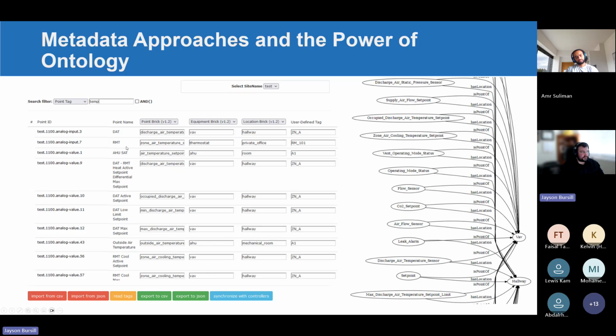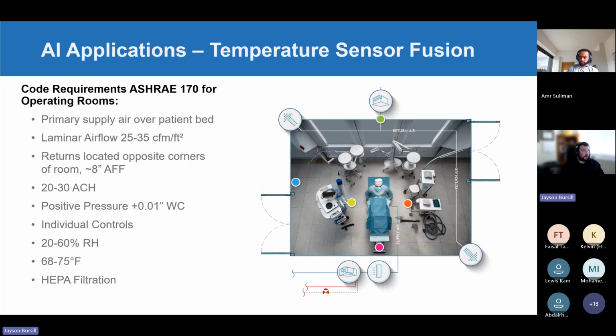This is supposed to be a tractable example where you can see DAT is discharge air temperature sensor, and how all of these relate to things like the VAV, the hallway, and other proper names and locations that would look like a bowl of spaghetti if I showed all of it. But you get the idea of how you can assign metadata tags taken from key value pairs, these tuples, and turn them into triples, building a larger map of the system that's ingestible by artificial intelligence systems.